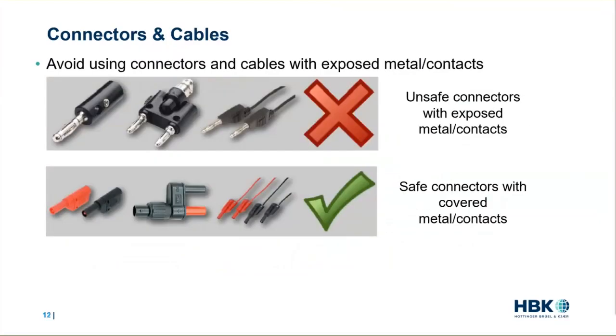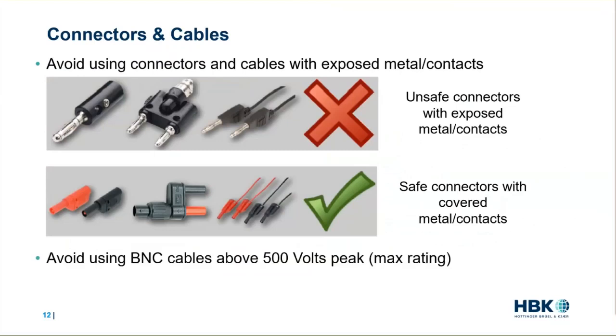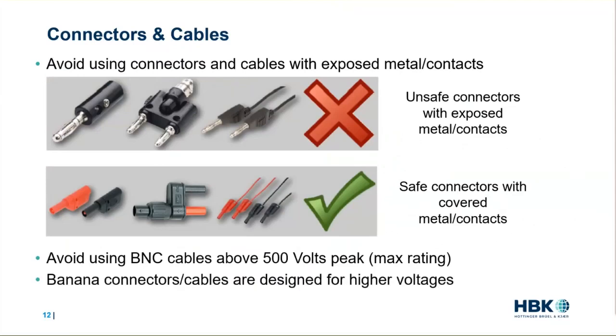Now, just a quick note on connectors and cables. You want to be sure to avoid using connectors and cables with exposed metal contacts, and instead be sure to use connectors and cables that do not have any exposed metal or contacts for ultimate safety. You also want to avoid using BNC cables above 500 volts peak, because that's their maximum rating. In fact, banana connectors and cables are designed for higher voltages.